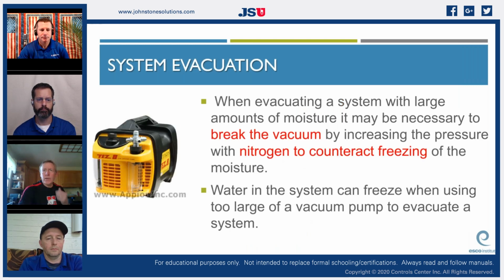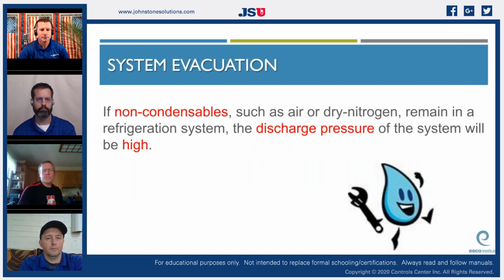We like to triple evacuate. Brian does this in his class, and I know Clifton does as well: evacuate it to 4,000 microns, I think, break it with nitrogen, down to 1,500, break it with nitrogen, and then down to your 500 or lower microns. Get triple evacuation.